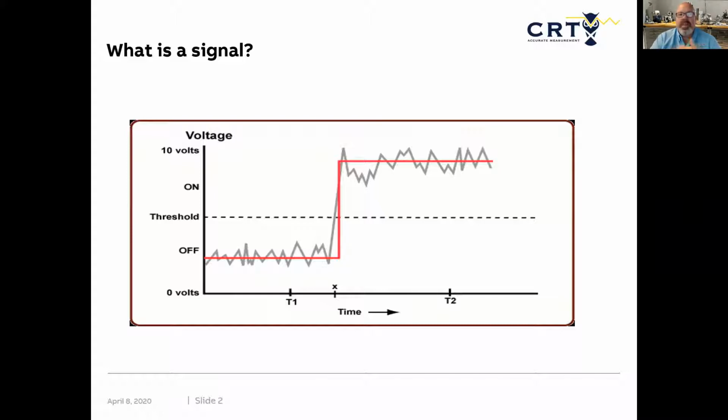The same way, if I sent the signal and it was at 6 volts, not necessarily what looks like 9 volts here, I would still count it as an on. I don't care if it's 6, I don't care if it's 9, I don't care if it's 24. What it's done is it's gone above the voltage threshold. And I'm going to show you where we set up the voltage thresholds, and also how you can determine what type of resistors and what type of inputs you're going to use to make sure that that signal is seen by the FlowX. Again, it's really simplistic.